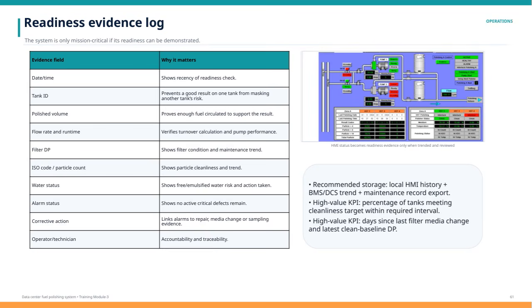One important point is that the HMI status only becomes valid readiness evidence when it's trended and reviewed over time. For best results, it's recommended to store this data locally on the HMI, as well as in a building management system or distributed control system for trend analysis, and to export maintenance records. Key performance indicators to watch include the percentage of tanks meeting cleanliness targets within required intervals and tracking days since the last filter media change, along with the clean baseline filter differential pressure. This thorough logging and analysis process helps guarantee that your fuel polishing system remains reliable and ready when you need it most.